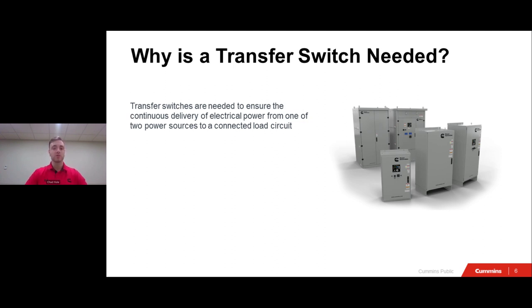You might recognize those emergency power sources as generators or other utilities being redundant in those situations. This then creates a need for something to monitor and transfer the power between these sources, which is exactly what a transfer switch does. An automatic transfer switch is responsible for quickly and safely transitioning all electrical power consumed by a circuit, equipment, or systems connected to the transfer switch output between those normal and emergency power sources.